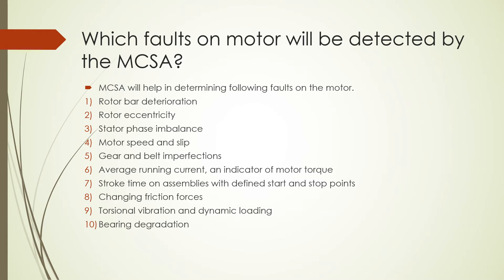The fourth question: which parts of a motor are detected by Motor Current Signature Analysis (MCSA)? MCSA helps in determining the following: rotor bar deterioration, rotor eccentricity, stator phase imbalance, motor speed and slip, gear and belt imperfections, average running current as an indicator of motor torque, stroke time on assemblies with defined start-stop points, changing friction forces, torsional vibration, dynamic loading, and bearing degradation.